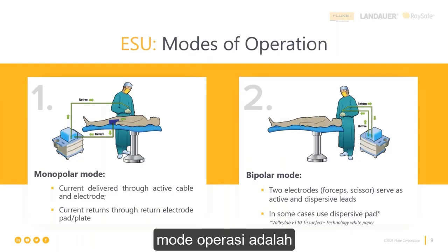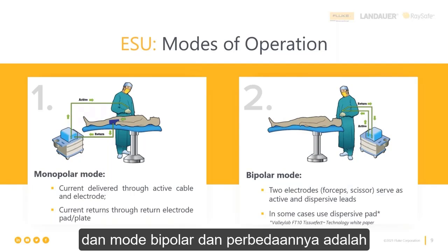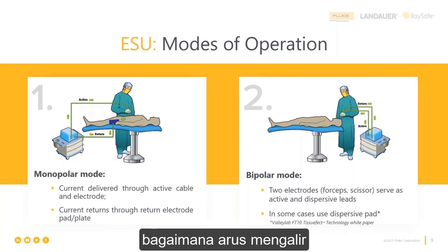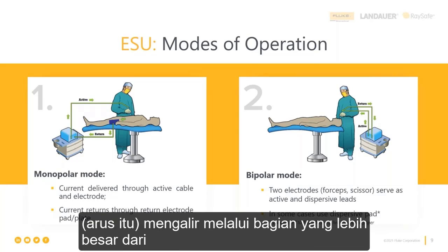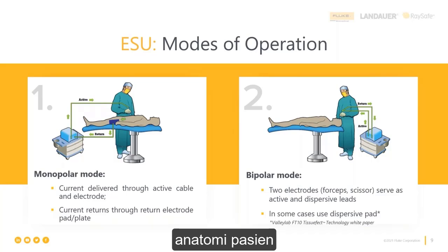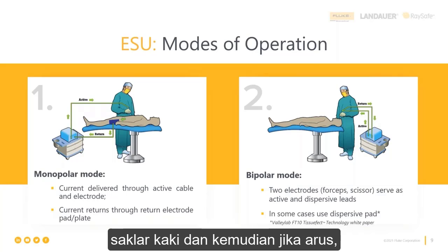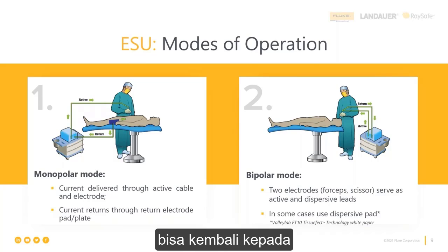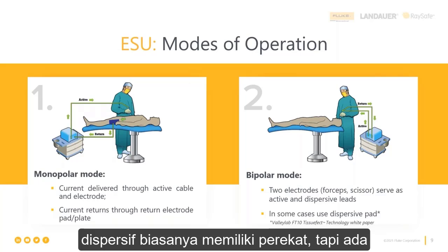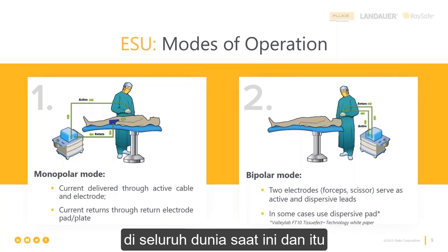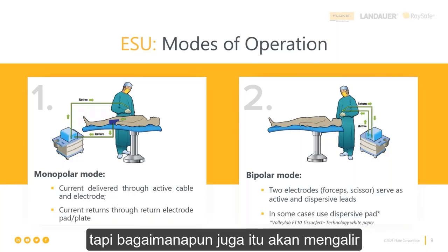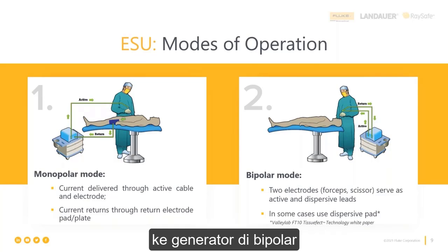Modes of operation include monopolar modes and bipolar modes. The difference, as you can see on the slide, is how the current flows and to what extent it has flowed through a larger portion of the patient's anatomy. In monopolar, we have an active electrode that's used for controlling cut and or coag, either through the handpiece or through the foot switch. And then for the current to flow, it has to be able to get back to its source. The way that's done is through a dispersive electrode pad, usually adhesive, but there are still some metal plates around in the world today, and those are certainly less safe. The gel pads are much safer, but in any case, the current flows through that dispersive electrode back to the generator.